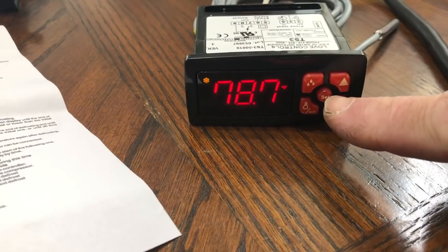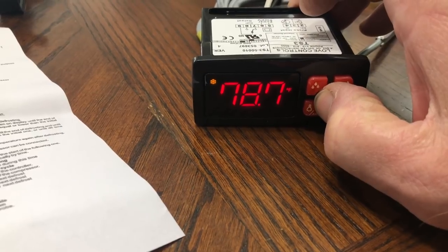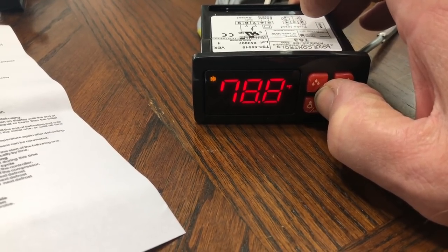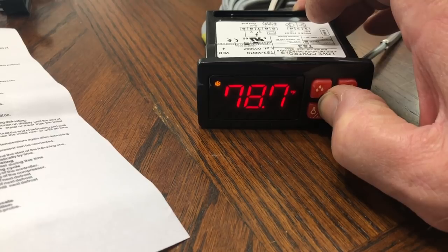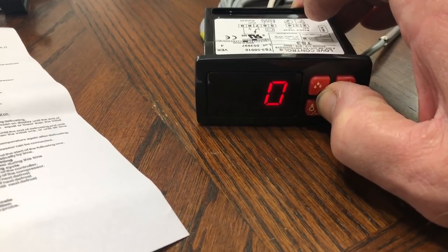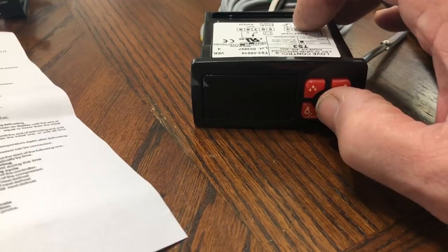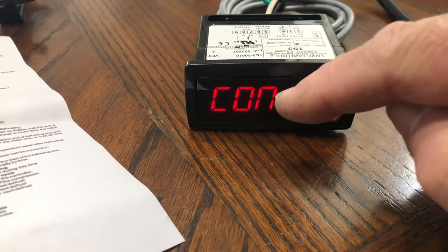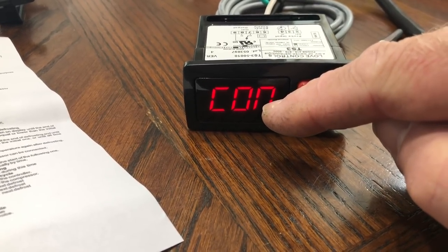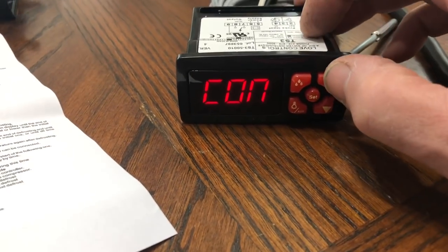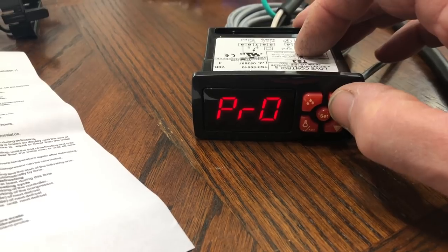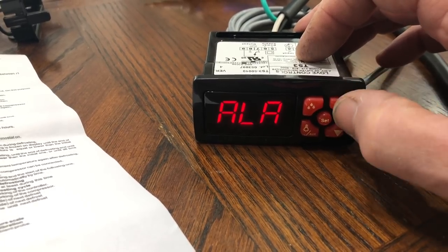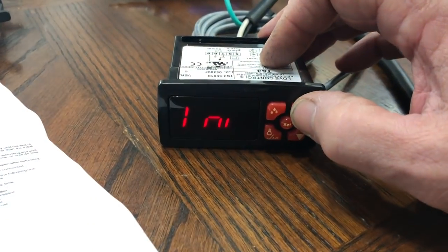And then let's get into this little bugger. So you're going to press the set button here in the middle for eight seconds. And we'll hold it down and see what it does here. And that gets us into our code, which was zero set. Now we're into our sub parameters. That's the CON section. That's the defrost section. That's the pro section. That's the alarm section. And that's your INI section.